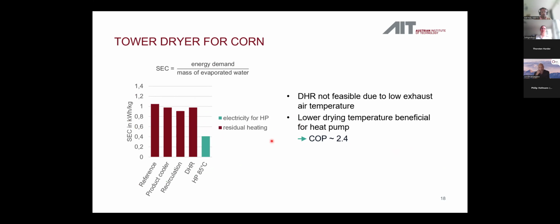That is the reason why, in this case, direct heat recovery is not possible, because the exhaust air temperature is not hot enough to still heat the fresh air coming into the dryer. We assume a minimum temperature difference of 20 degrees, which is not given there. So there is no potential for direct heat recovery.